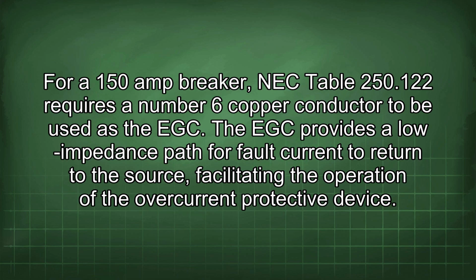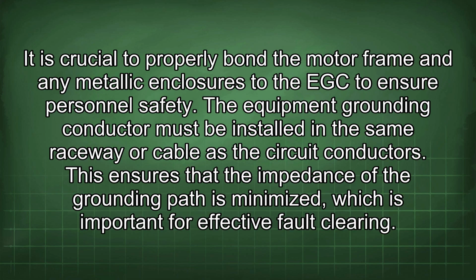The EGC provides a low impedance path for fault current to return to the source, facilitating the operation of the overcurrent protective device. It is crucial to properly bond the motor frame and any metallic enclosures to the EGC to ensure personnel safety. The equipment grounding conductor must be installed in the same raceway or cable as the circuit conductors. This ensures that the impedance of the grounding path is minimized, which is important for effective fault clearing.